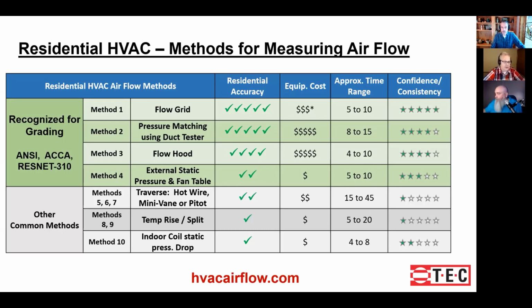A duct traverse, many of you know, is sort of the gold standard in commercial airflow measurements. And for good reasons. It's a good way to do it in commercial applications, and oftentimes the only way to make that measurement in commercial stuff. However, it kind of falls apart in a residential situation for a couple of reasons. The first one is that you don't normally have enough straight duct in a residential situation to get that measurement.